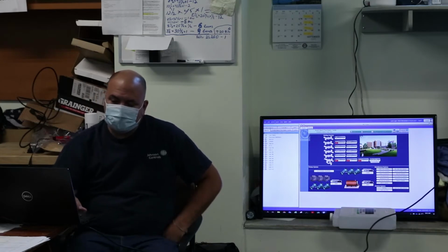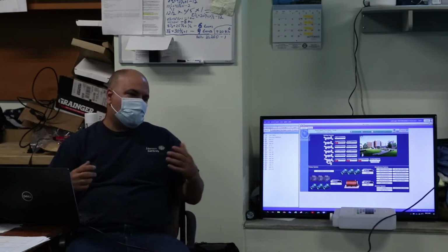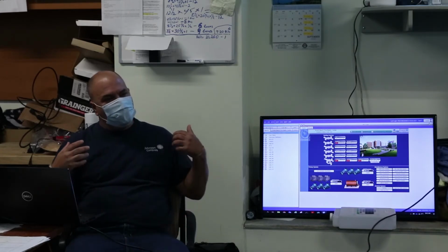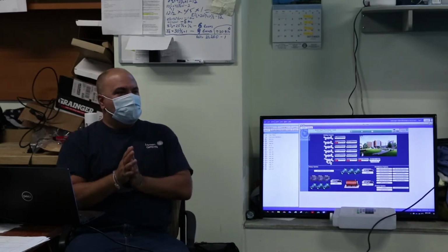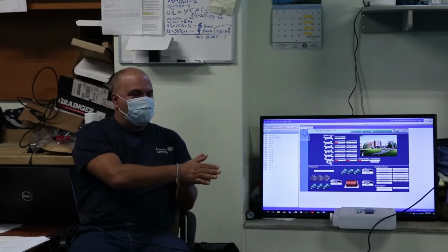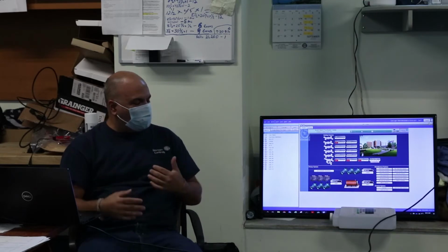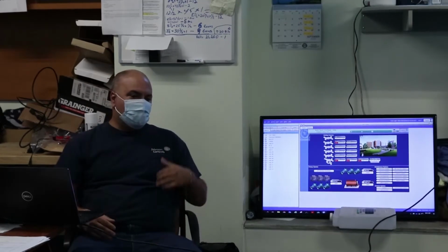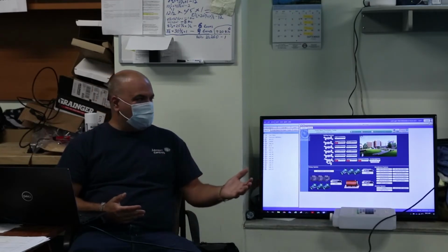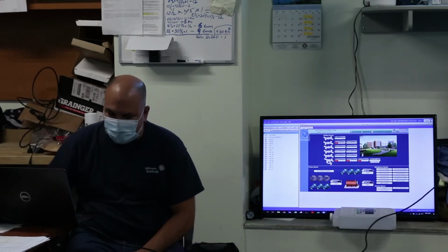Okay, so what we're going to start with is I'm going to show you guys how to set up a user view with a summary definition. And what we'll do is I'll show you how to take the VAVs that are associated with the air handler that feed it and put them into separate categories. So if you wanted to look at all the VAVs for, say, AHU5, you could click on a folder and see all the VAVs for AHU5.